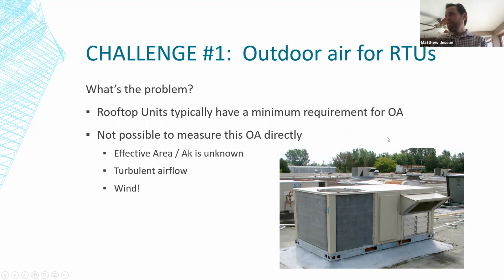If you take a look at this picture, you see the hood where the outdoor air comes in. What is my effective area going to be there? We talked about how the area of your airstream isn't the same as just the area of the opening. Could I take a Velgrid or something and put it up against this and get a reading? I certainly could, but I don't know what to do with that reading. I don't know what to multiply it by. I could take a guess, but that could be all over the place.